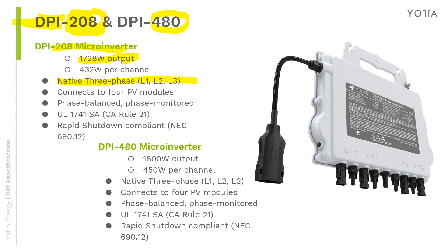This is gold right here, because this is phase monitored and phase balanced. Phase monitoring: if you lose a phase, it will shut down the entire inverter, making it safe. Phase balancing: you no longer have to use single phase inverters and balance around the triangle, the A, B, and C. It's all done inside the device. Again, phase monitored and phase balanced, really nice plug and play.